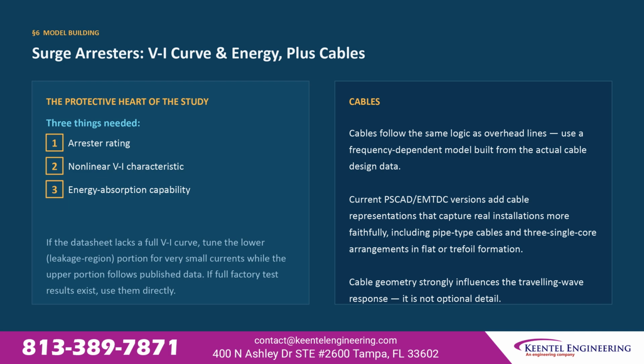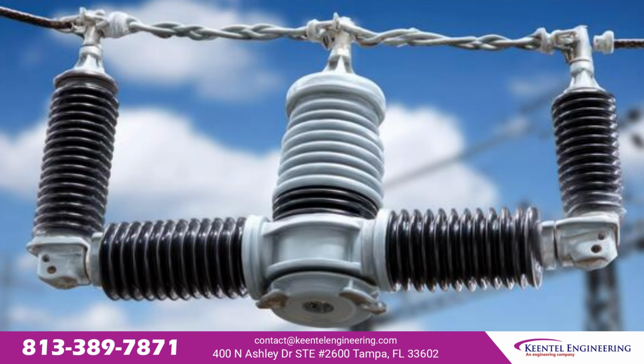A frequency-dependent model built from actual cable design data. PSCAD/EMTDC versions support pipe-type cables and 3 single-core arrangements in flat or trefoil formation. Cable geometry strongly influences the traveling wave response and is not optional detail.